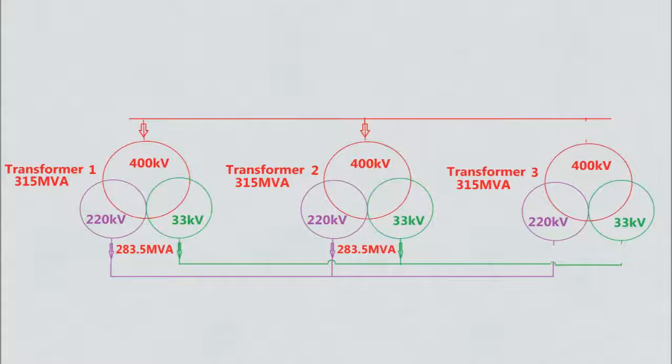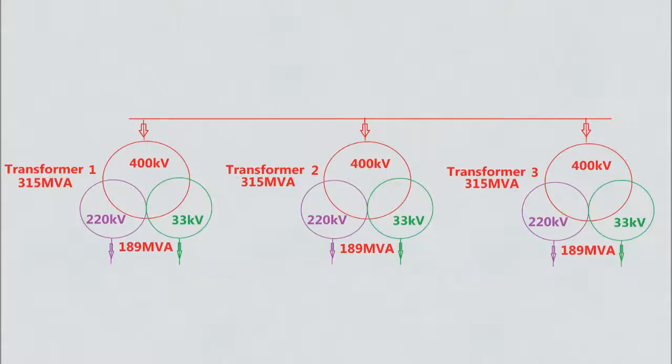Now Transformer 3 can be taken out by opening the isolator and then applying proper earthing at the working points. This is how parallel operation of transformers is done. To bring the transformer back into service, exactly the reverse procedure is followed — that is, after removing earthing and closing isolators, the 400 kV side is charged first, and then the 220 kV and 33 kV sides are charged.